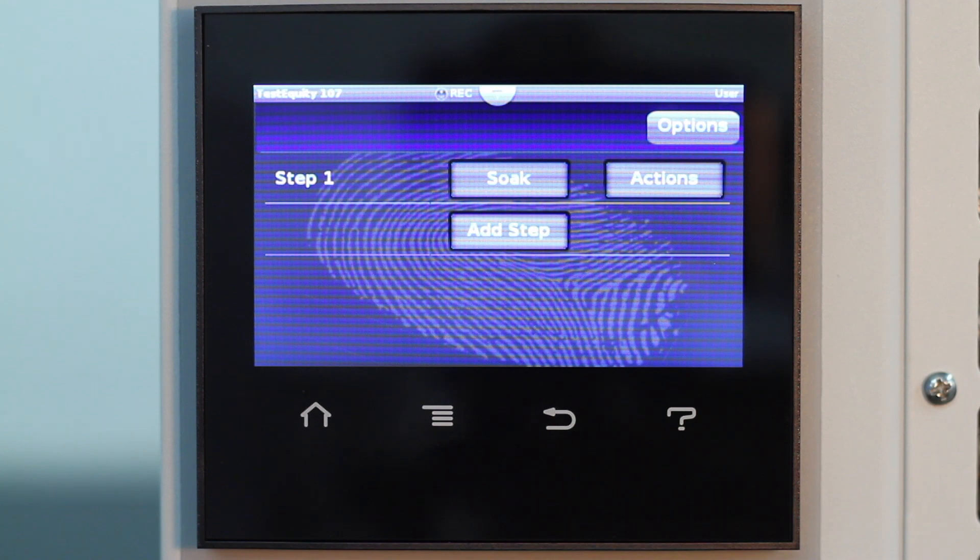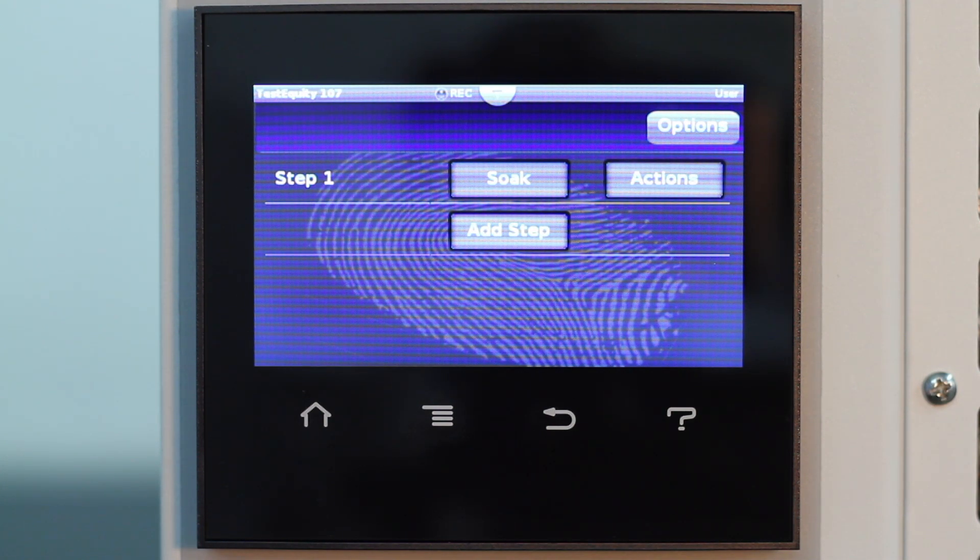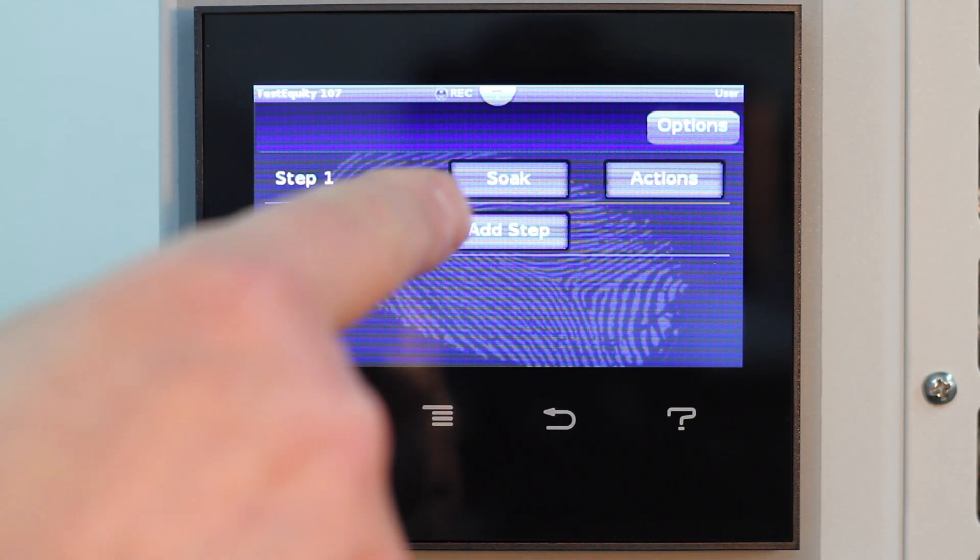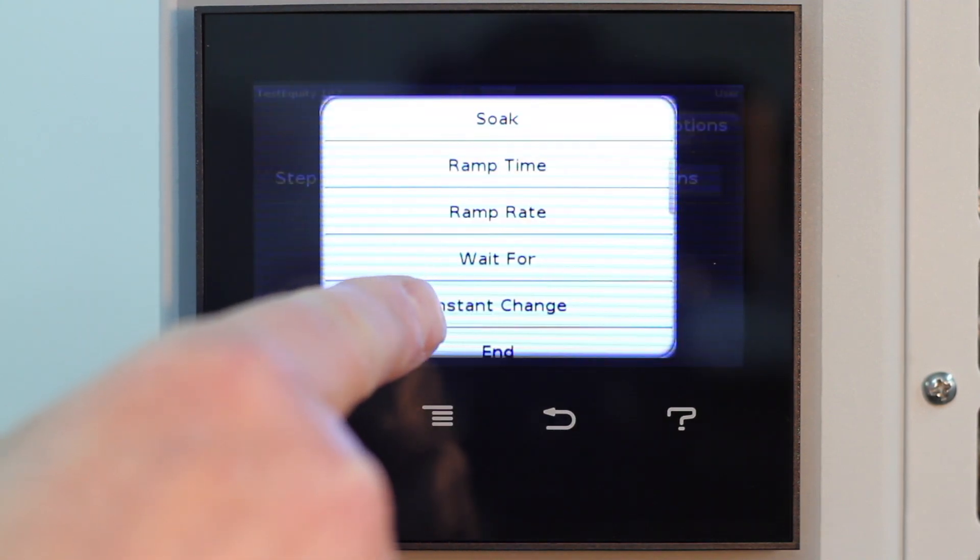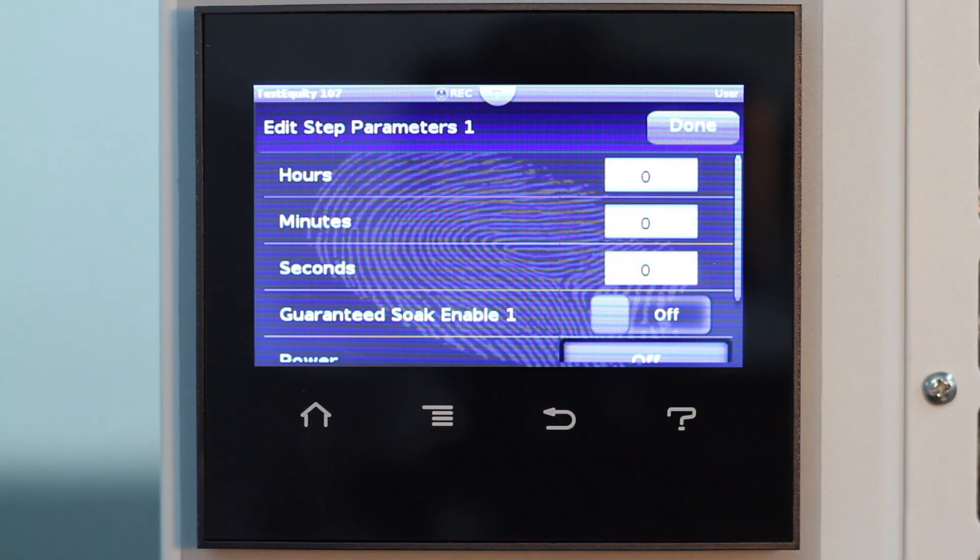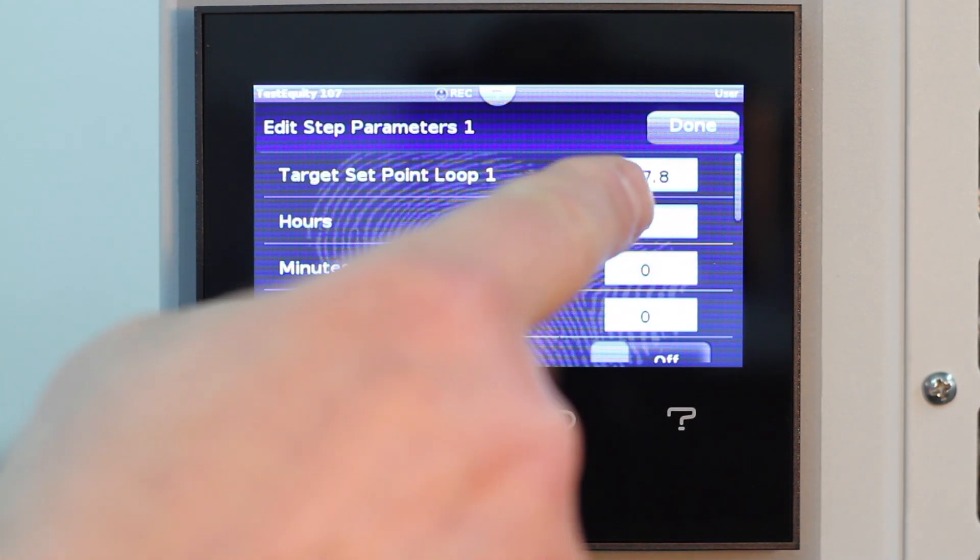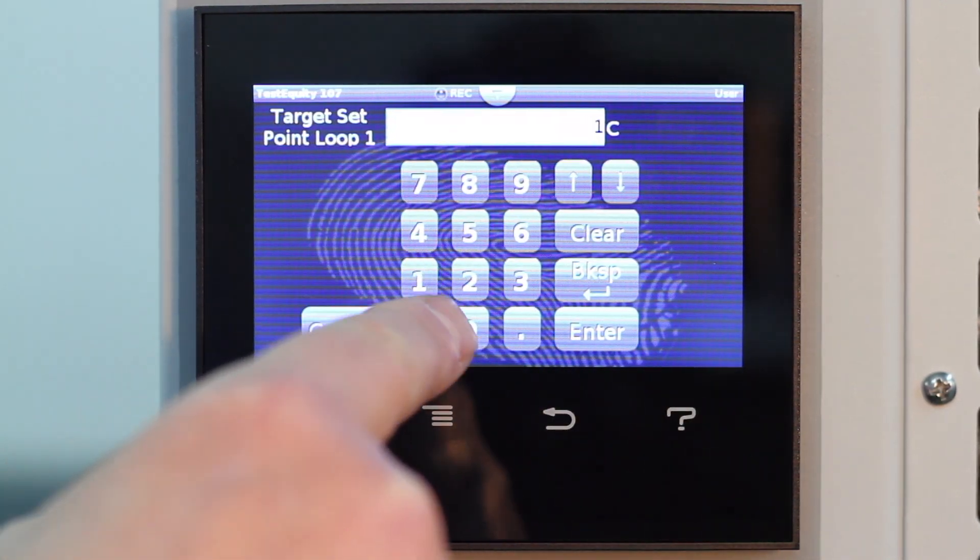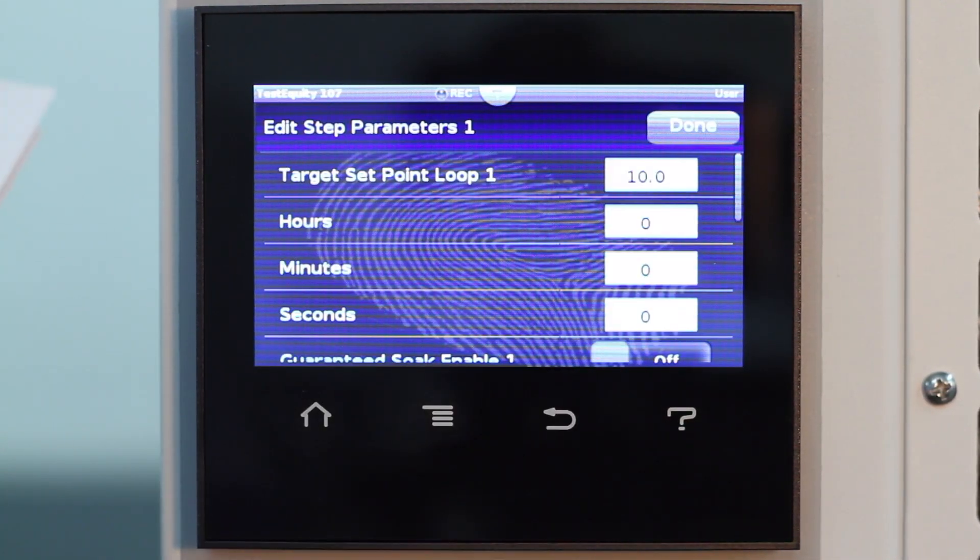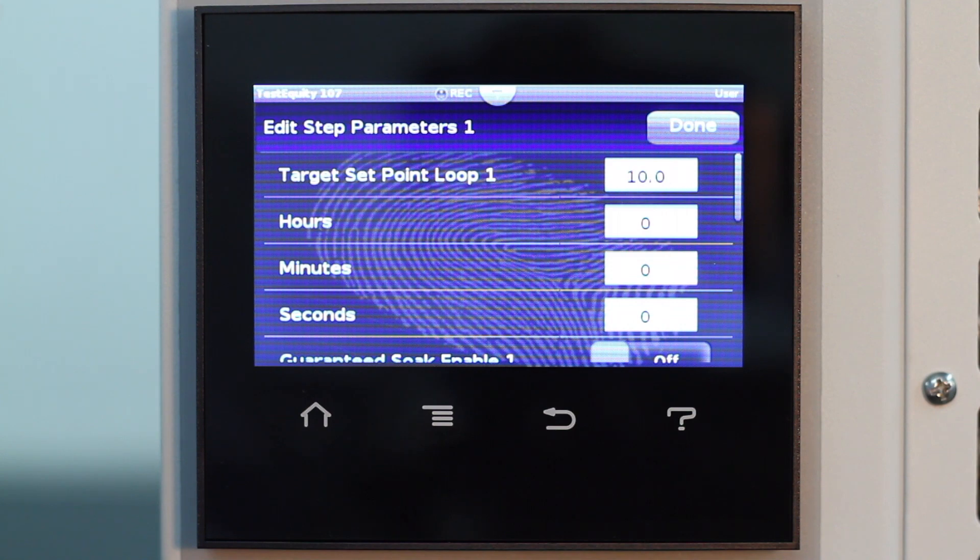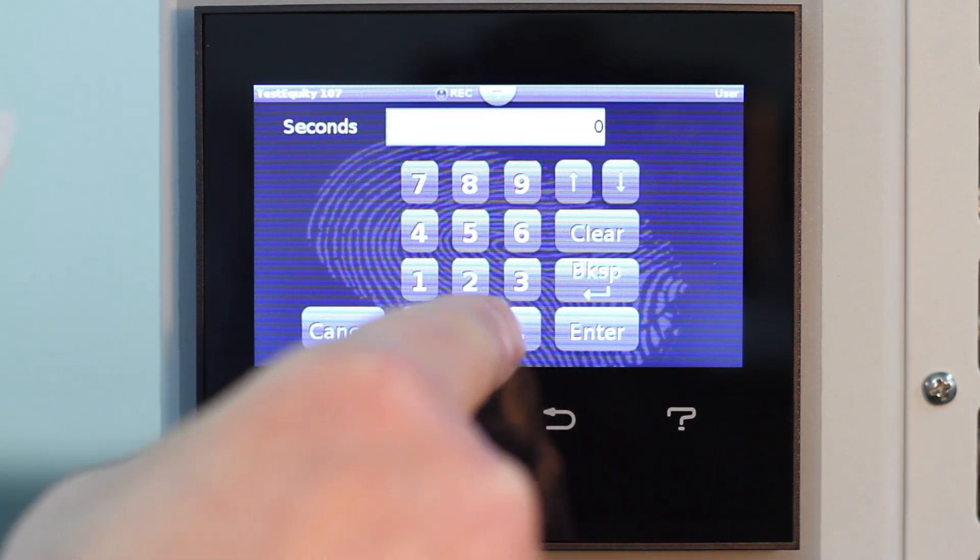For step 1, we are going to select Instant Change for the step type. We can combine an instant set point change and soak time in this single step. The target set point is 10 degrees C. The time to stay at this step is 30 seconds.